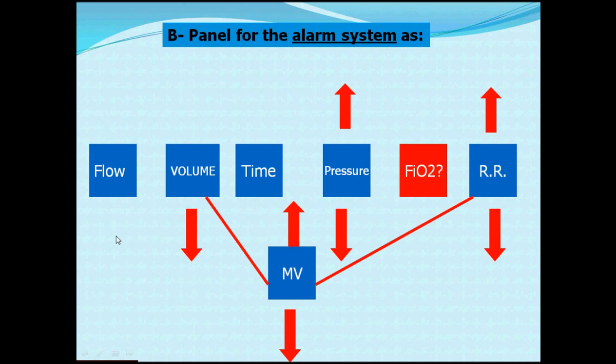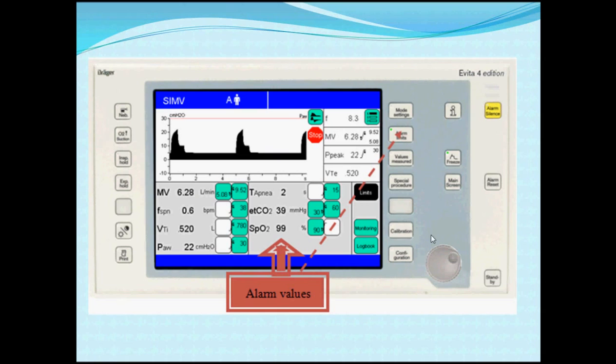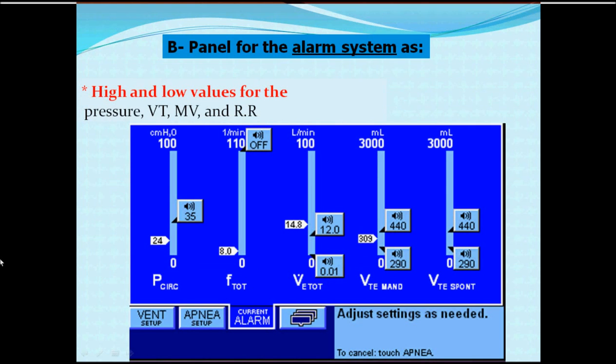The alarm system is very important and is often highlighted because most respiratory therapists and doctors managing ventilators frequently forget to set it. The alarm must be set specifically for each patient on the ventilator. Settings include: how much the tidal volume should decrease before alarming, what minute volume range triggers an alarm, what pressure limits — high or low relative to set values — generate an alarm, and what respiratory rate thresholds should alert you.